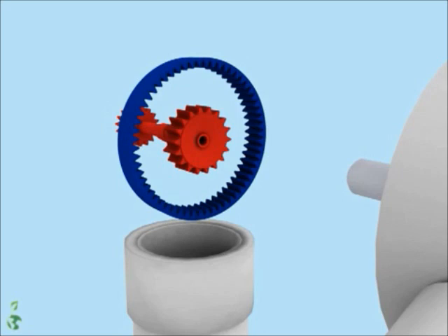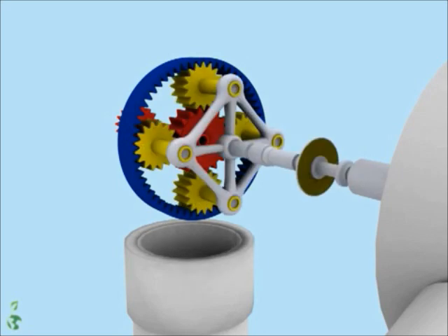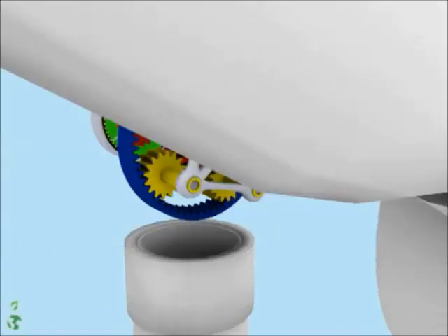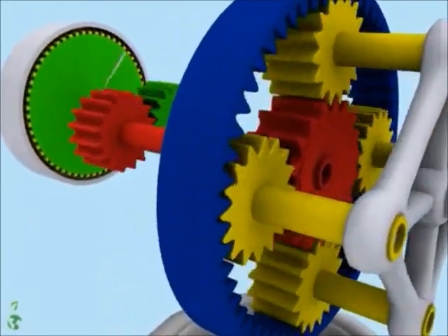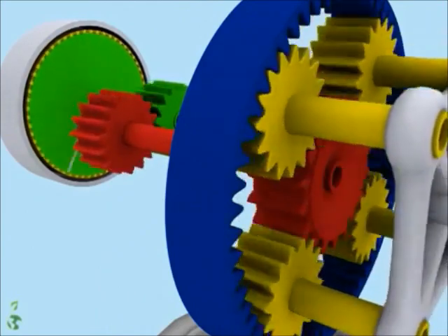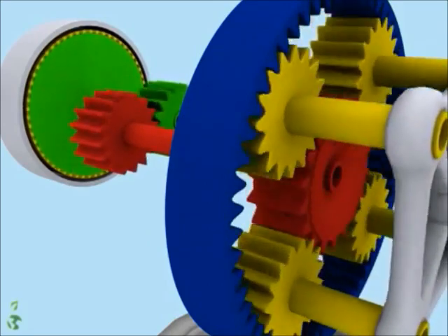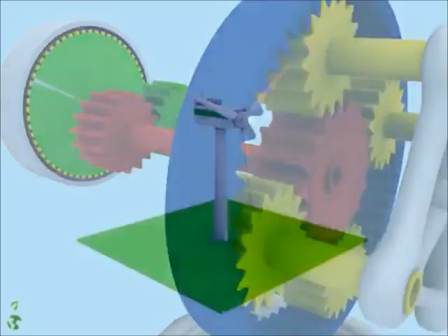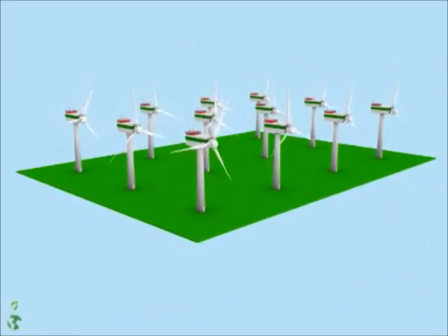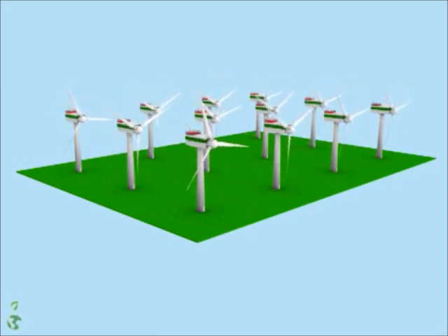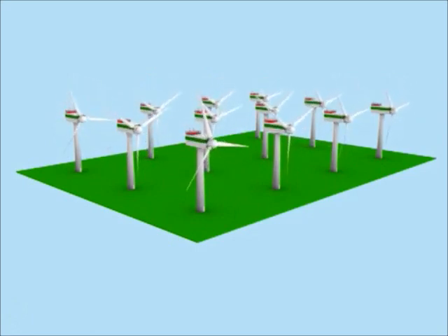The sun gear in the middle is meshed with four planet gears. An electromagnetic brake is applied when the wind velocity is too high. When the rotor spins, the planet gears drive the sun gear, which in turn drives the shaft of the generator to produce electric power.